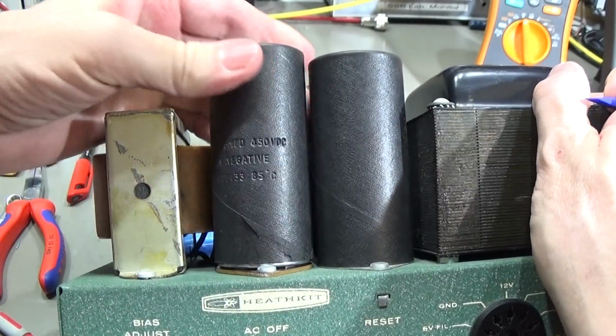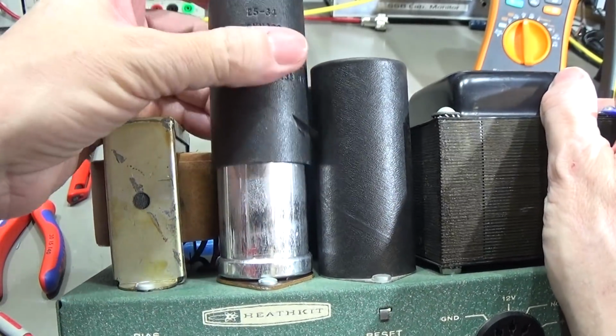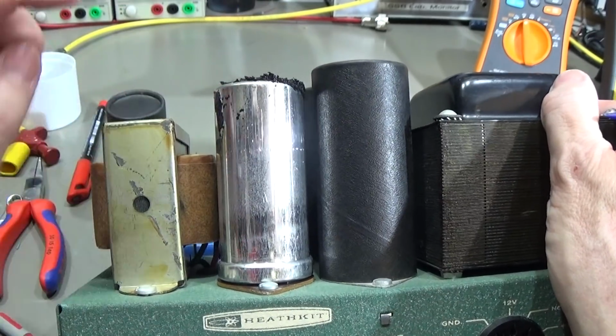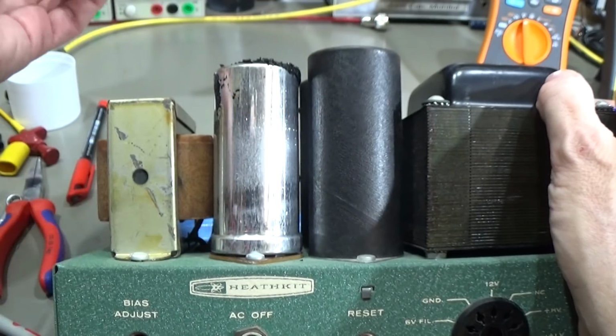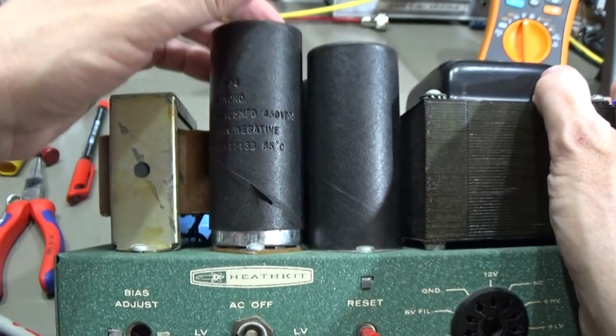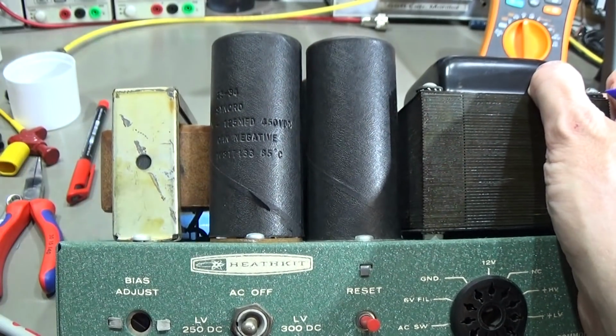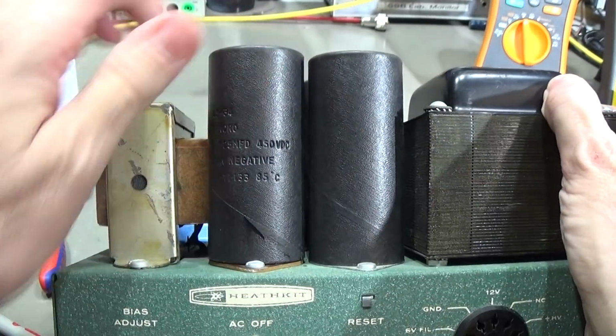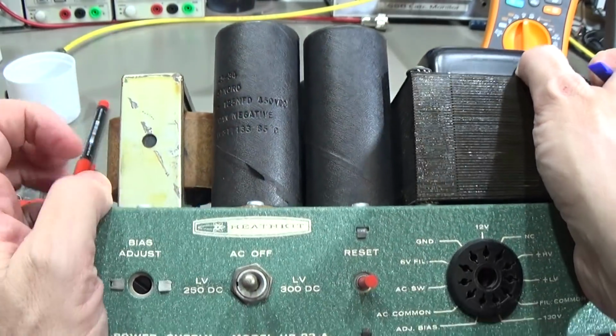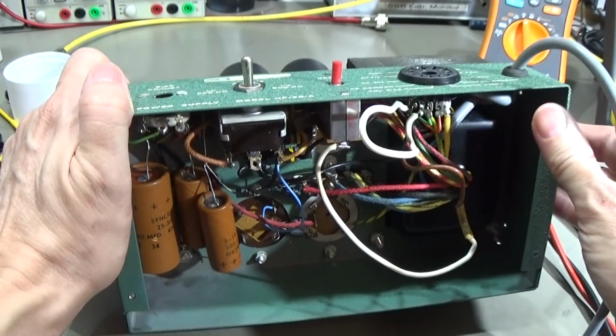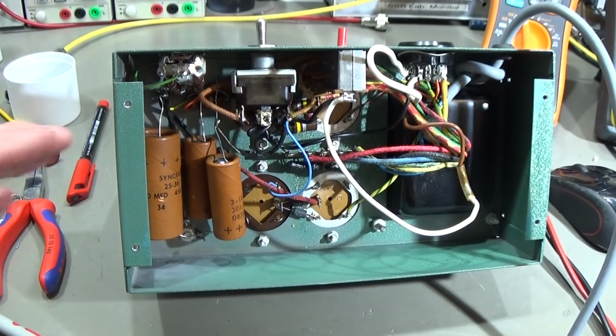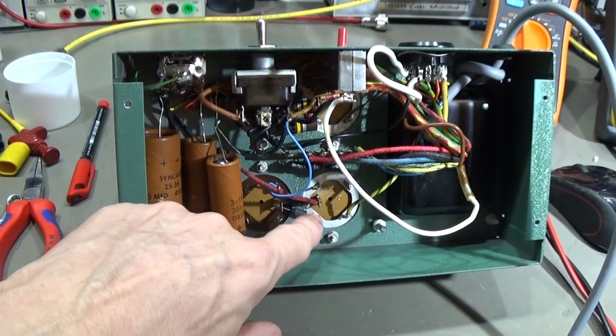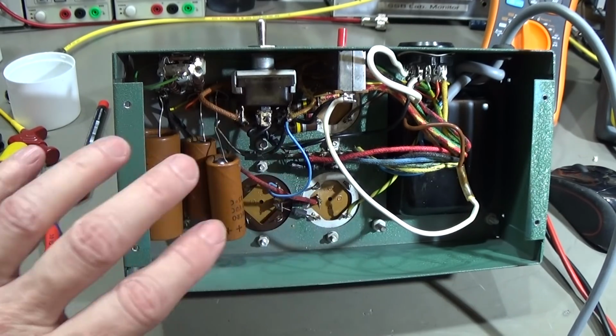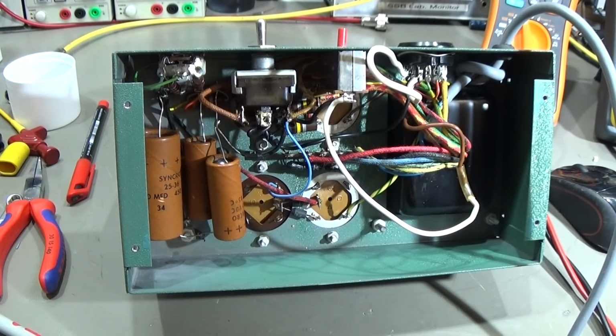By the way, I haven't shown that - this is only a sleeve over the original can, but that makes no difference in general. When I apply 450 volt DC to each of the capacitors to test for leakage, I have to disconnect the rest of the circuit to be sure nothing else gets damaged.